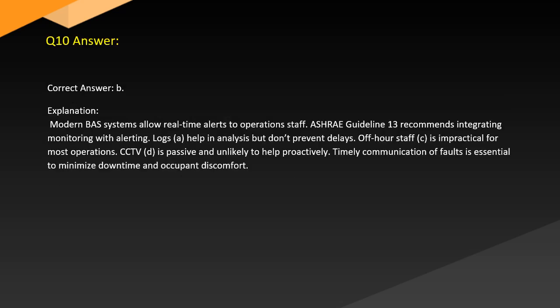Answer. Correct answer: B. Explanation: Modern BAS systems allow real-time alerts to operations staff. ASHRAE Guideline 13 recommends integrating monitoring with alerting. Logs (A) help in analysis but don't prevent delays. Off-hour staff (C) is impractical for most operations. CCTV (D) is passive and unlikely to help proactively. Timely communication of faults is essential to minimize downtime and occupant discomfort.